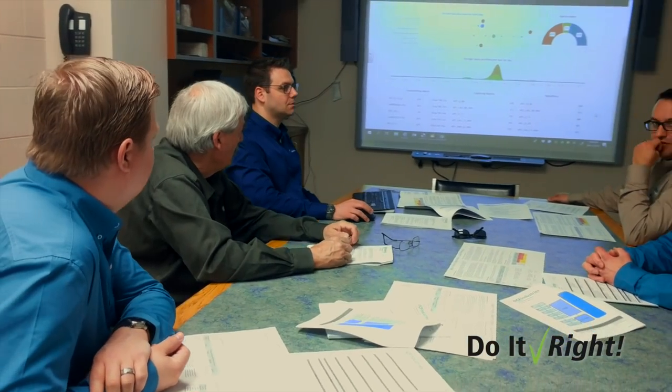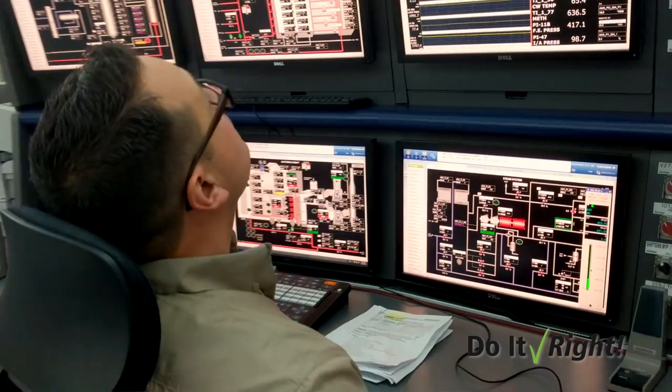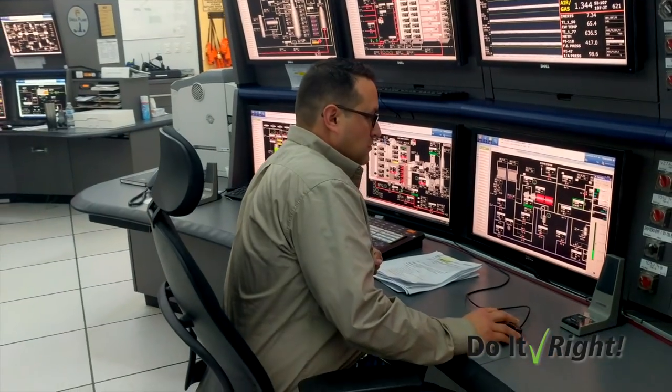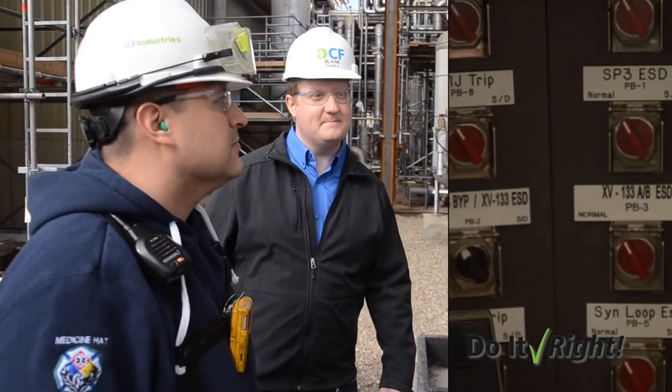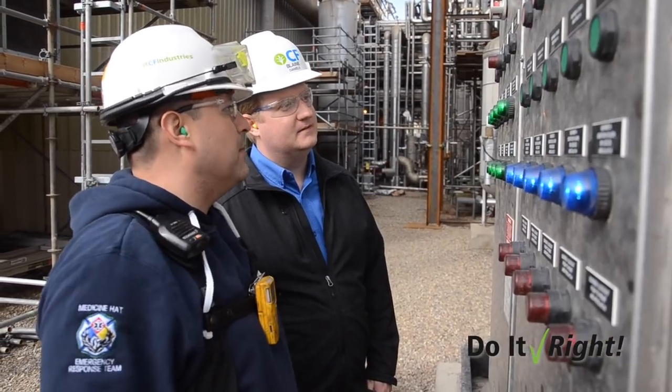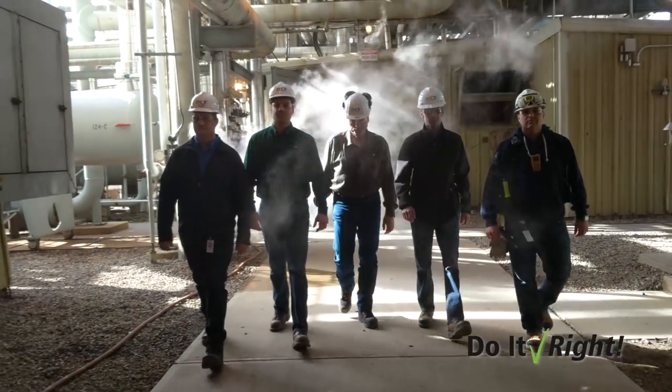If we assign a higher priority to a pre-warning, where I can intervene and hopefully correct the situation before we lose a piece of equipment or have people getting hurt, that has a lot more value to me as a board operator. What the alarm consultants helped us to understand was you have to move to a predictive alarm system. And by being predictive, you give yourself time to then prevent that consequence. You have to look at every single alarm on its own basis and its own value.